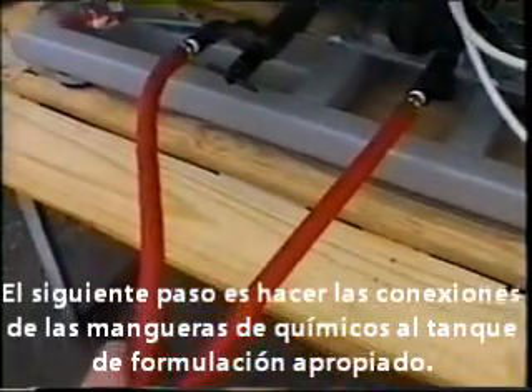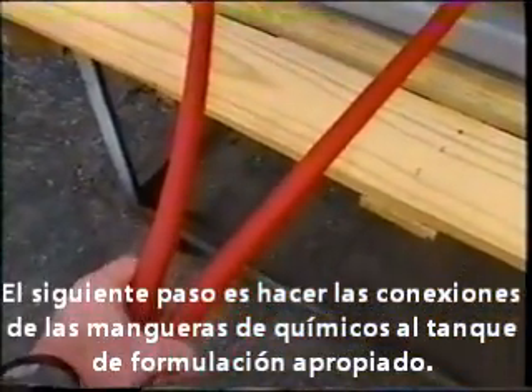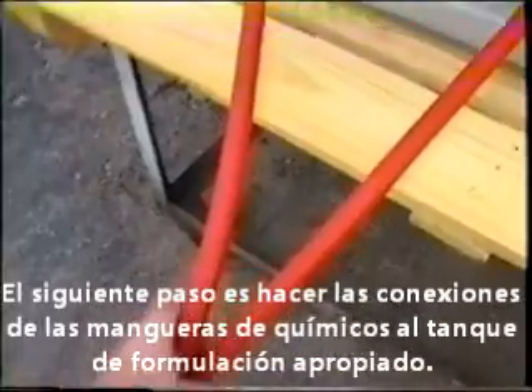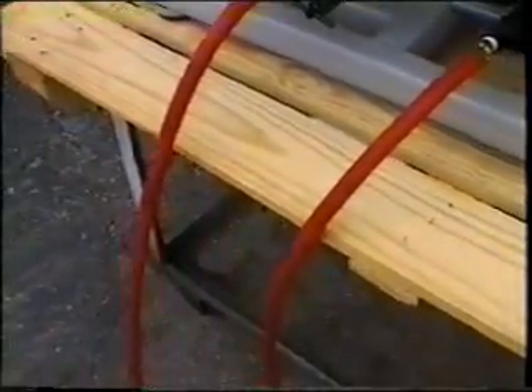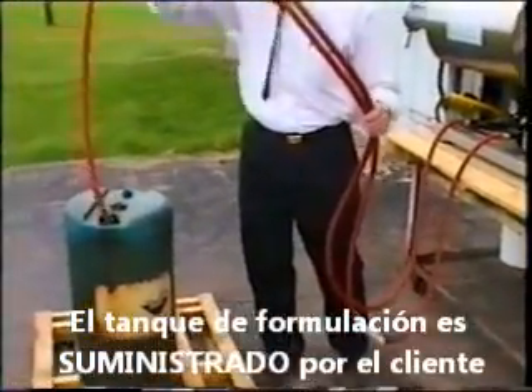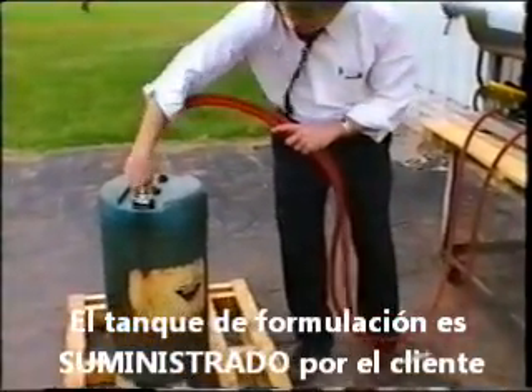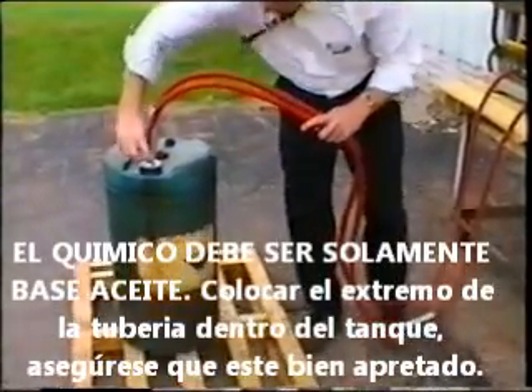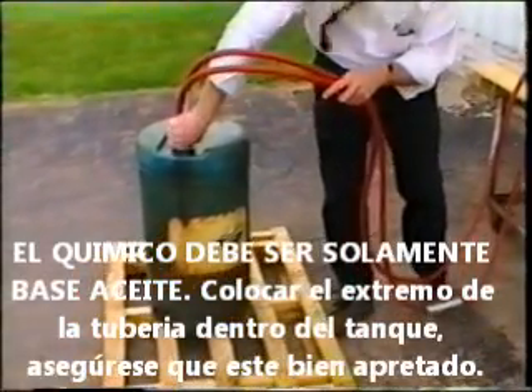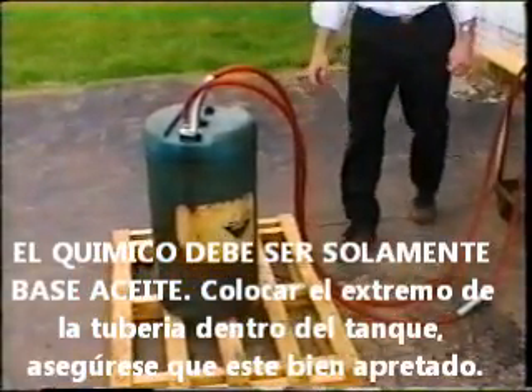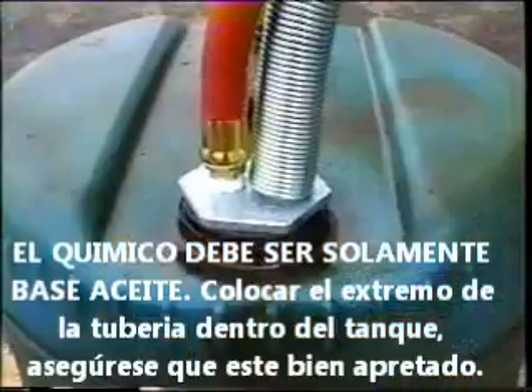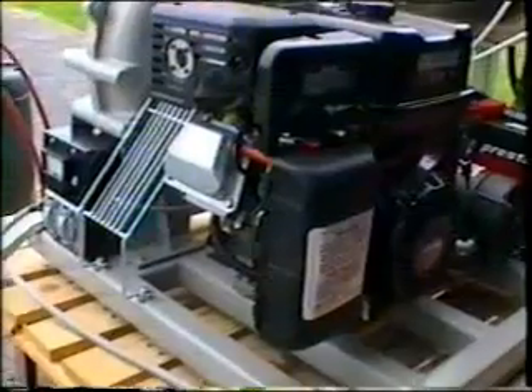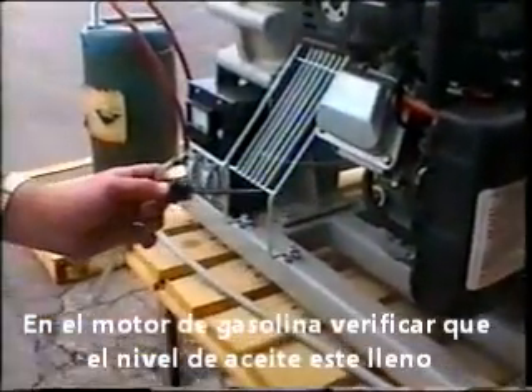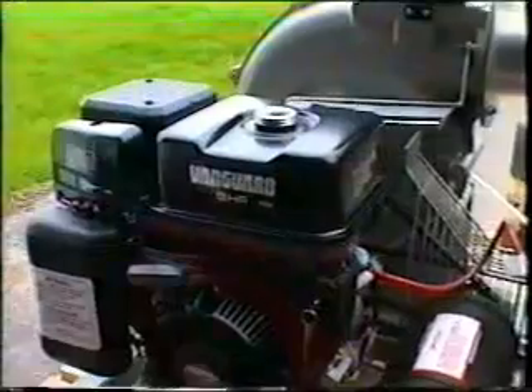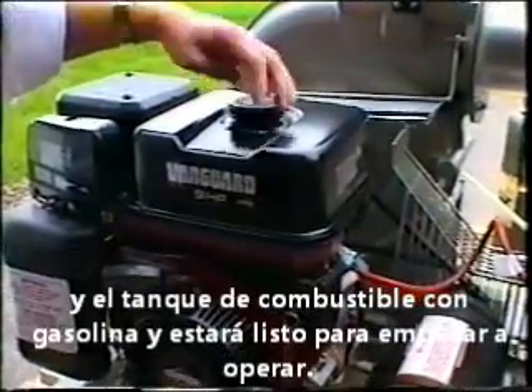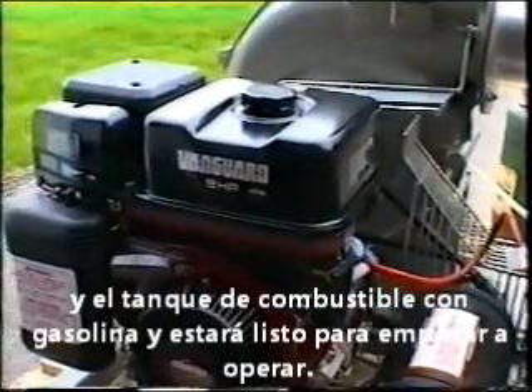The next step is to make the connection of the chemical pickup tube and the return line to a proper chemical tank. The chemical tank is supplied by the customer. The chemical must be an oil-based product. Submerge the end of the pickup tube into the chemical container and make sure that the lid is tightened. On the gasoline engine, make sure that the oil level is full. Add gasoline to the fuel tank and you are ready to begin operation.